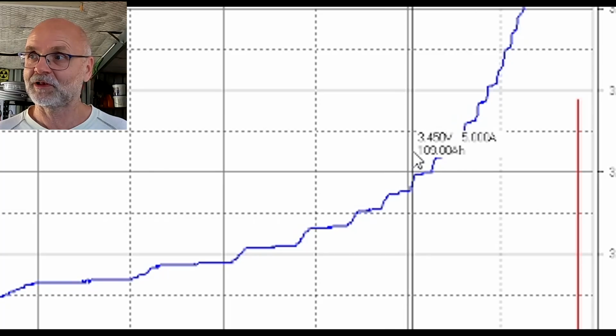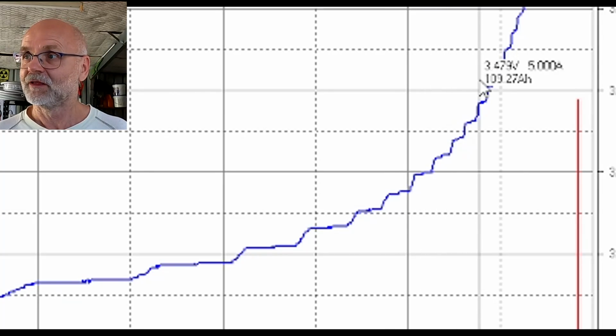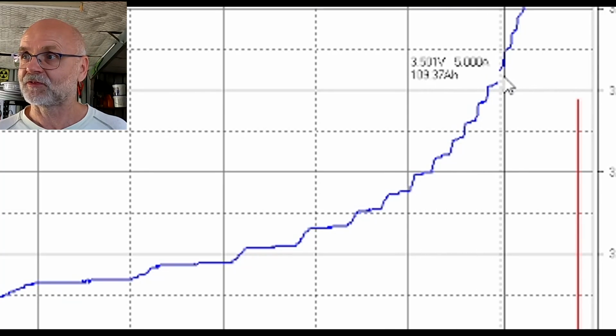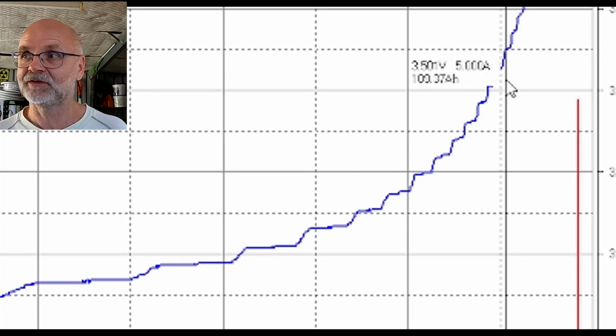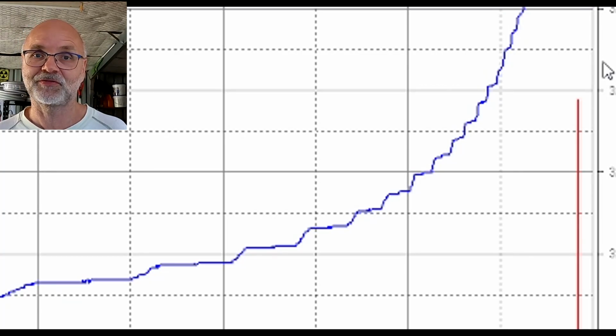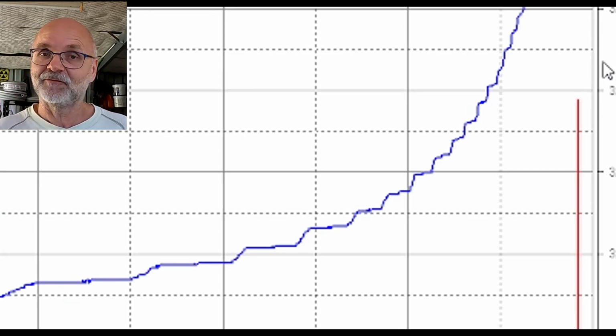It goes very quickly up, and at 3.5 I set the charge controllers to go into absorption mode. This is over here. This is 109.37. Yeah, this is 0.3 of an ampere hour missing from there to 3.65 volts. But again, higher voltage, more stress.